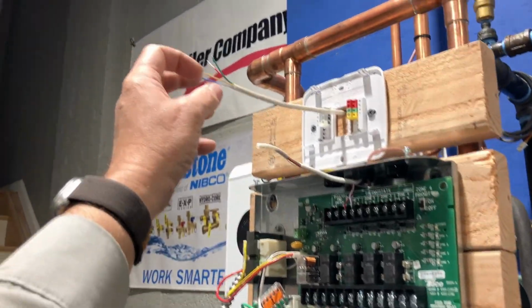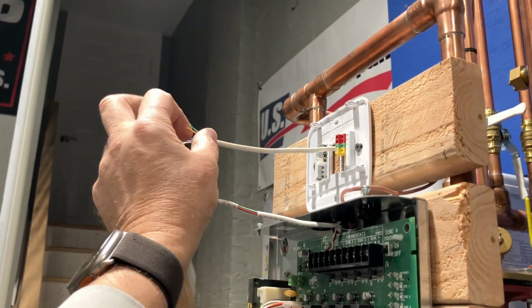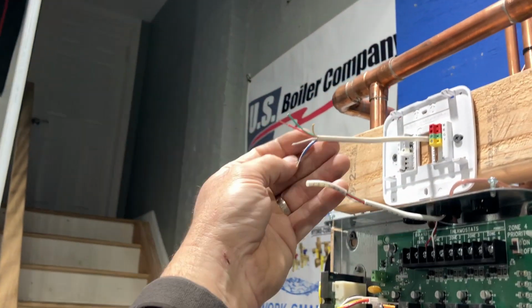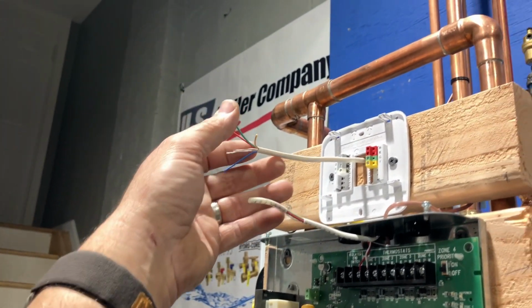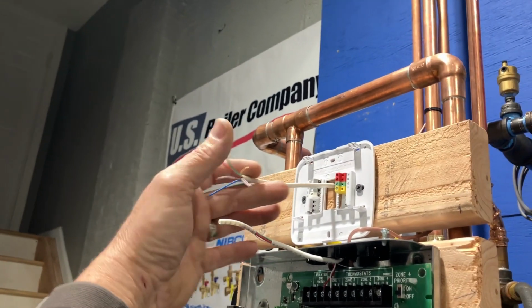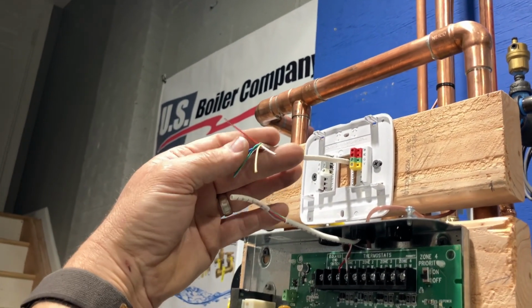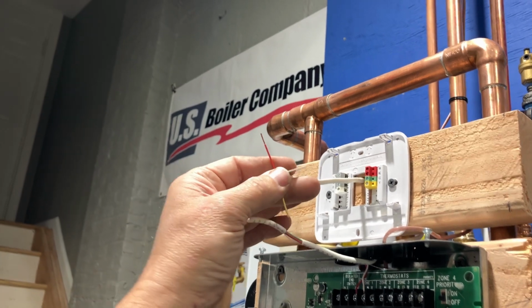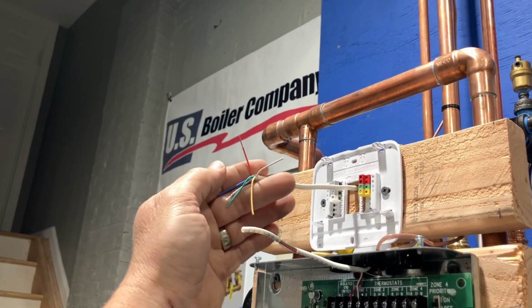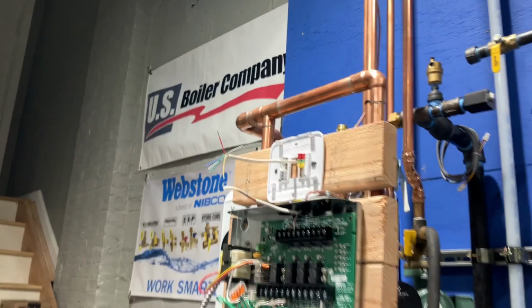Yellow and common? Wrong. Well, if you're going to use industry standard, yellow would be Y, and common would normally be blue. Okay? But since we're heating only, industry standard is that we're going to use the red wire for RH and the white wire for W. Okay? The other three wires are not going to be used here.